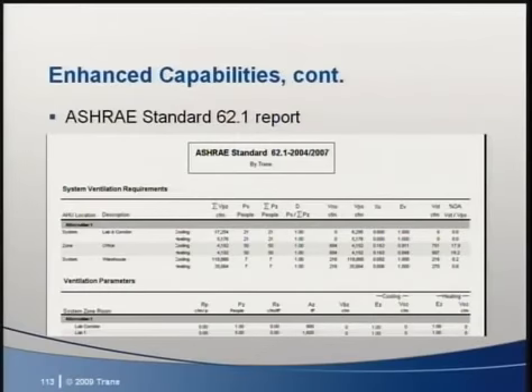So as discussed previously, prerequisite 1, minimum IAQ performance for the indoor environmental quality credits, requires that at a minimum, mechanical ventilation systems shall be designed using the ventilation rate procedure of Standard 62.1. A new ASHRAE Standard 62.1 report has been created in order to view detailed components of the 62.1 calculations that are used to determine outdoor air requirements. This new report can also be used to aid in attaining credit 2, increased ventilation, which requires 30% greater outdoor air ventilation rates as compared to the minimum of Standard 62.1 2007.